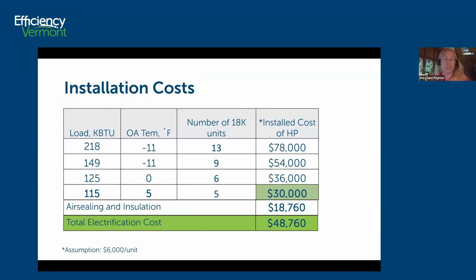Installation costs, my assumption was $6,000 per unit, meaning per 1-to-1 unit in the 1 to 2 ton range. And looking back at the original load of 218,000 BTU, you would need about 13 1.5 ton units, which would cost you $78,000. But on the flip side, if you were to size only for 5 degrees and you did thermal shell upgrades, now your costs are only $30,000. So significant first cost savings in heat pumps, going from 13 units to 5 units. Yes, you're still going to have some use of the boiler.